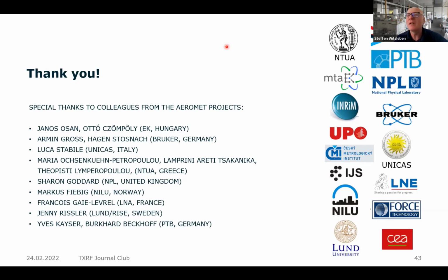I think so. So in my point of view, the most critical issue is the sample preparation and not so much the measurement procedure. Yeah, it depends. As I said, cascade impactor sampling provides samples which are unusual for TXRF, and you have to face the challenge of laterally extended samples or deposits. We have found out, which I could not show here because those were very recent results, that proper positioning of such a sample in a TXRF spectrometer is of extreme importance.